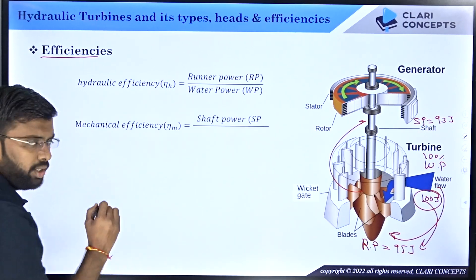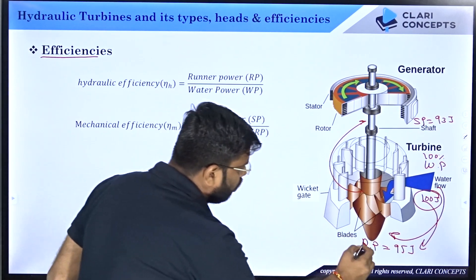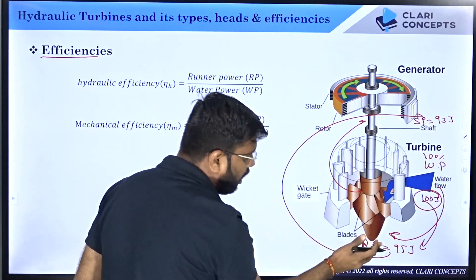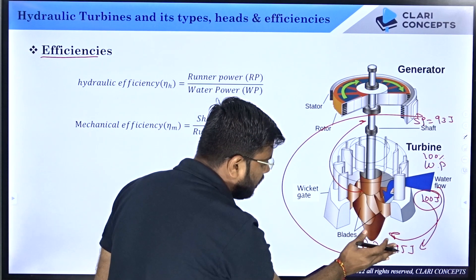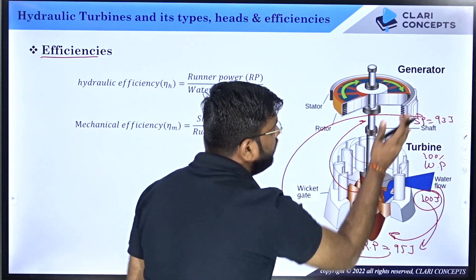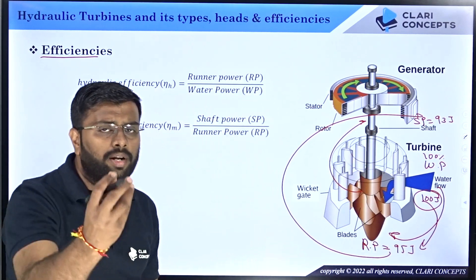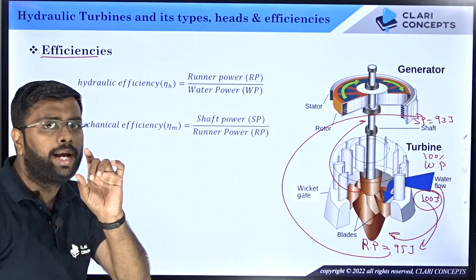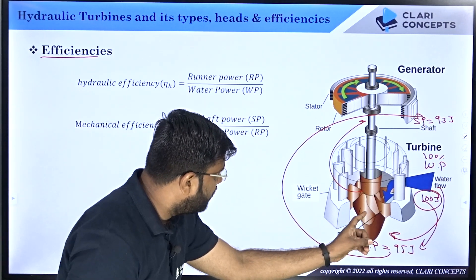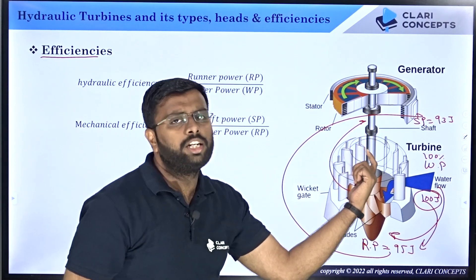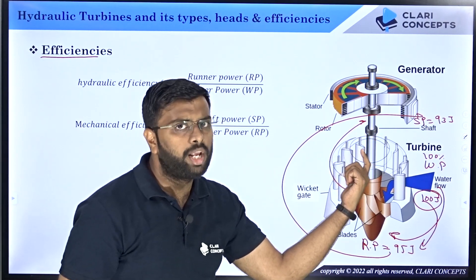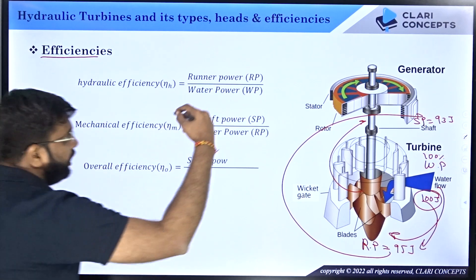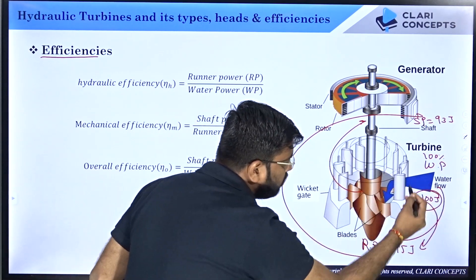Second is mechanical efficiency. This is the conversion from runner power to shaft power — for example from 95 joules to 93 joules. So mechanical efficiency is shaft power divided by runner power. The runner power is so much available, and that percentage which is transferred to the shaft is the mechanical efficiency. Mechanical efficiency eta_M equals shaft power divided by runner power.